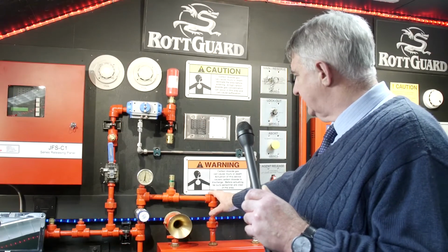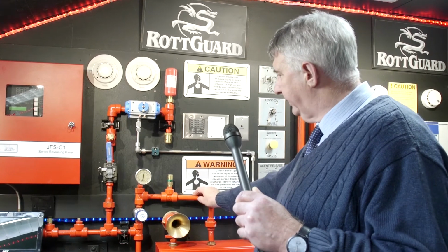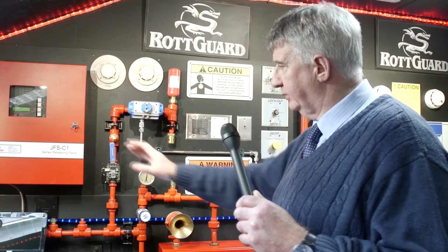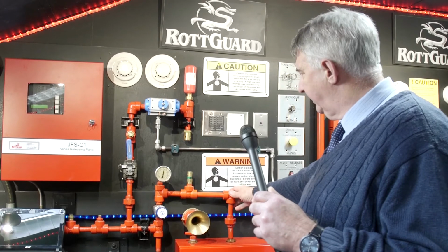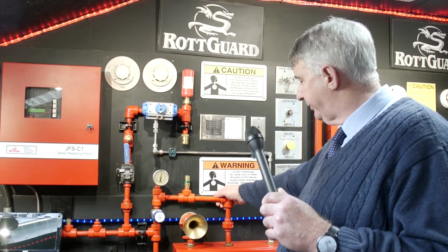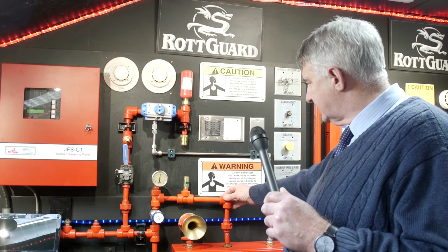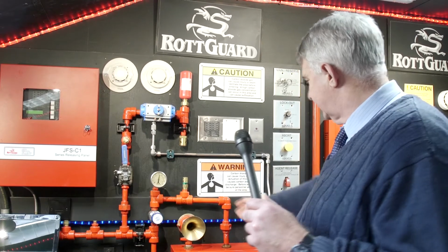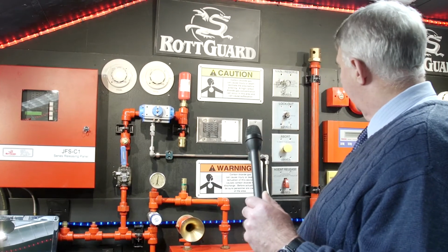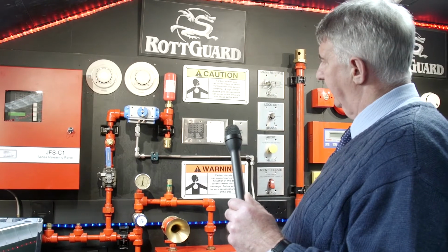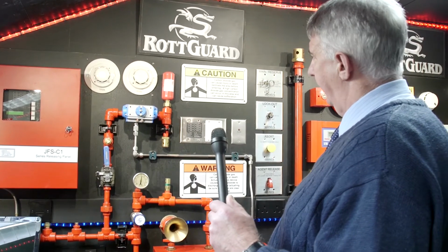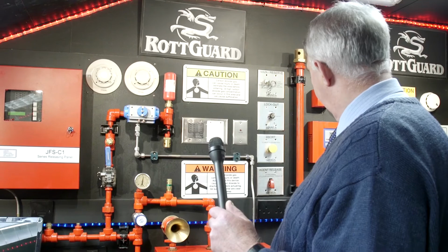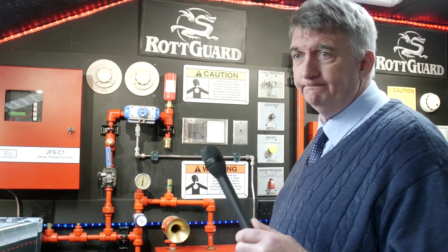You can see in this instance here that the pipe work associated with this system is Schedule 80 pipe, which is of a higher pressure rating, and these are 3,000 pound fittings as compared to the Schedule 40 pipe for this system, where the pressure rating is significantly lower.